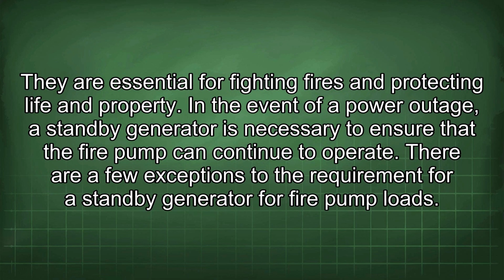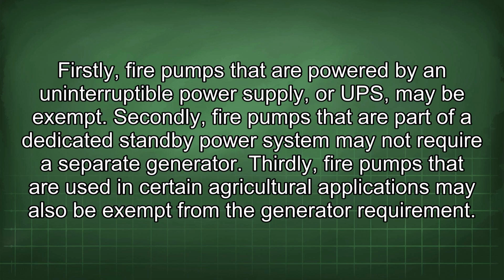In the event of a power outage, a standby generator is necessary to ensure that the fire pump can continue to operate. There are a few exceptions to the requirement for a standby generator for fire pump loads. Firstly, fire pumps that are powered by an uninterruptible power supply or UPS may be exempt. Secondly, fire pumps that are part of a dedicated standby power system may not require a separate generator. Thirdly, fire pumps that are used in certain agricultural applications may also be exempt from the generator requirement.